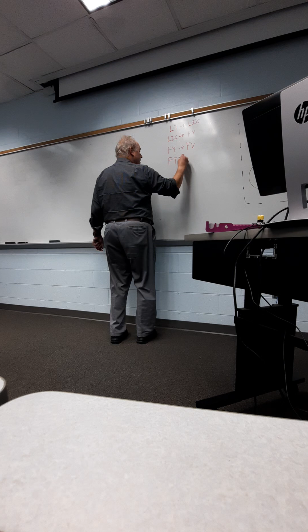What seems to be the primary loop here? Flow or level? Level is the primary loop. There is a flow loop involved as well, but it's subservient to the level. We're really adjusting flow to get a level, not adjusting level to get a flow. The flow loop is pretty tight—we adjust the valve, meter comes back to controller, that's your entire loop for flow.